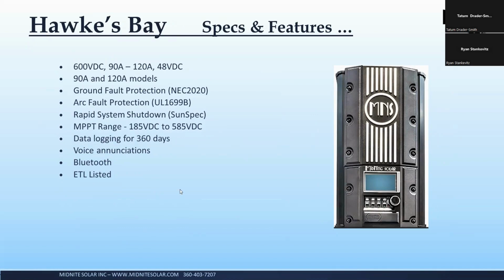The high voltage is nice where it just allows you to do fewer strings. Like on a Hawke's Bay 90, which we're getting ready to talk about, you can do one pretty hot string, or on the 120, you might do 2 strings in parallel, but it allows you to really minimize the combiner box issues, wiring, a lot smaller gauge wire. It's a real elegant way to go, especially if you have any distance to run at all.